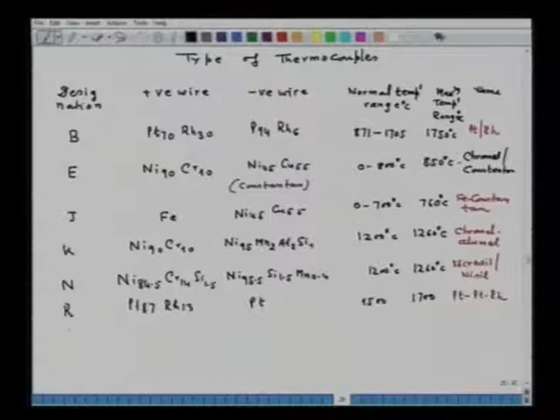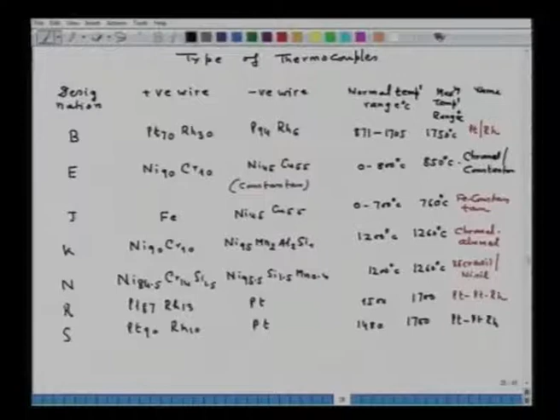And then you have R. In the R we have platinum 87, rhodium 13. It can go up to 1500 degrees Celsius, maximum is 1700 degrees Celsius, and the thermocouple is known as platinum rhodium thermocouple. Then again we have one more variety, that is S, which is platinum 90, rhodium 10. Platinum is the negative wire, it can go up to 1480 degrees Celsius, maximum is 1700, and it is also named platinum rhodium thermocouple.